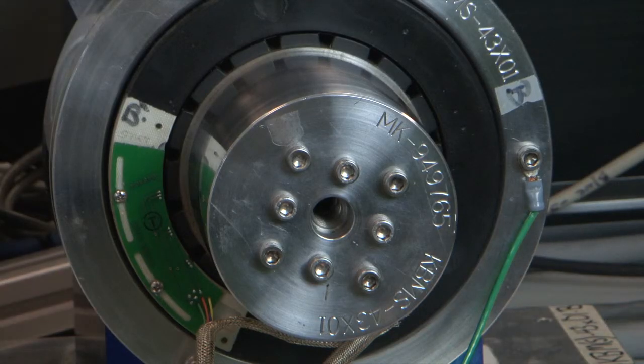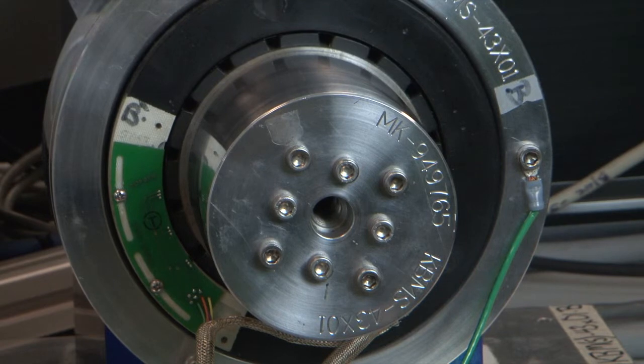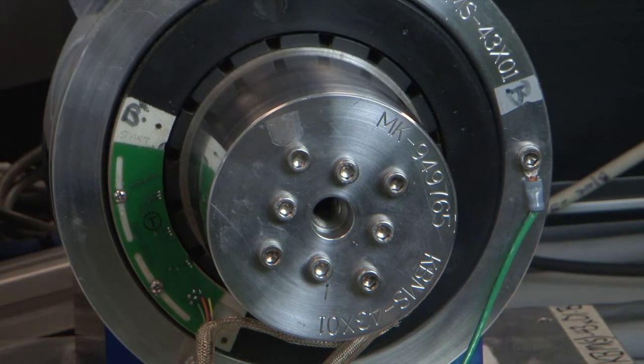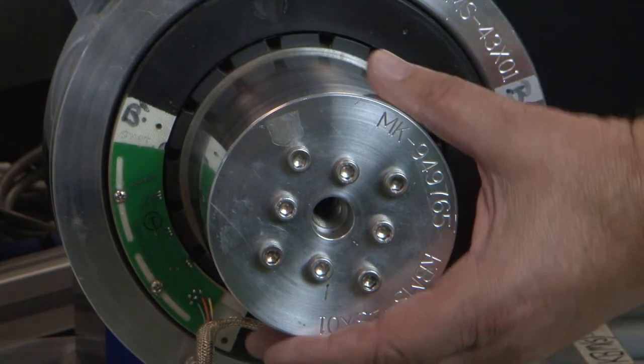One of the tell-tale signs that the feedback and motor are running in opposite directions from each other is the tendency for the motor to run away when disturbed.